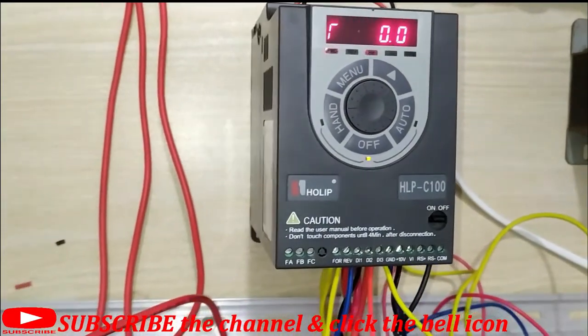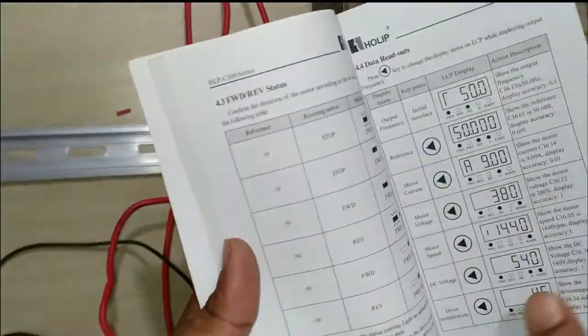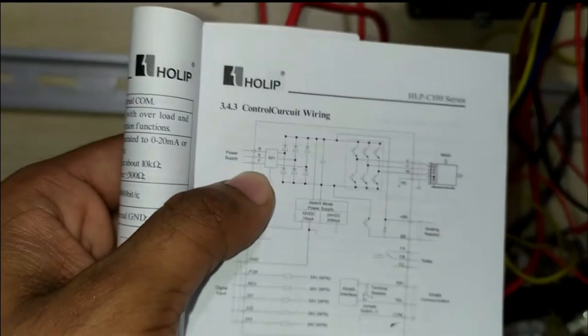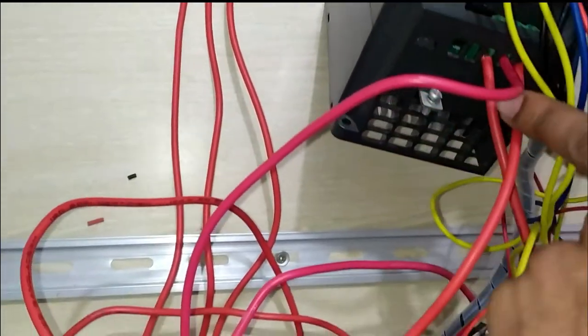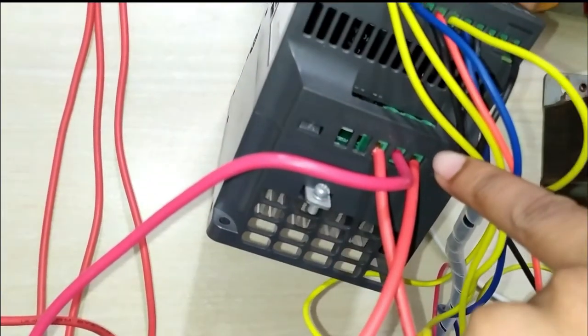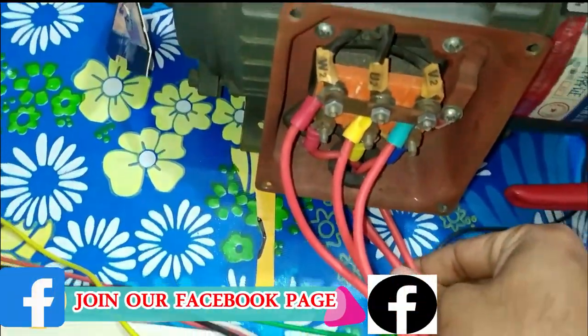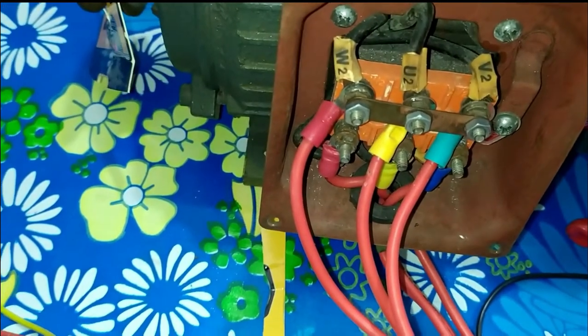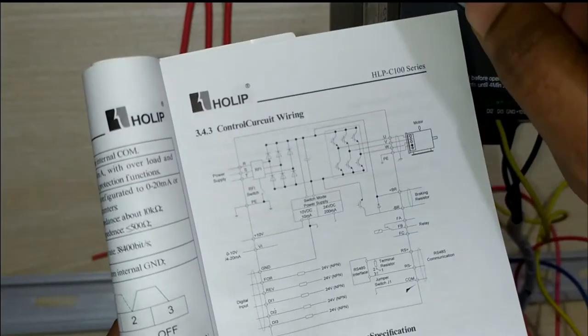First I want to describe the connection diagram of the Holip C100 series. RST terminals are connected directly to the power input — 220V line on RS. The output terminals are U, V, and W, which are directly connected to the motor by connector. The motor terminals U1, V1, W1 and U2, V2, W2 are shorted so the motor runs in a star connection.